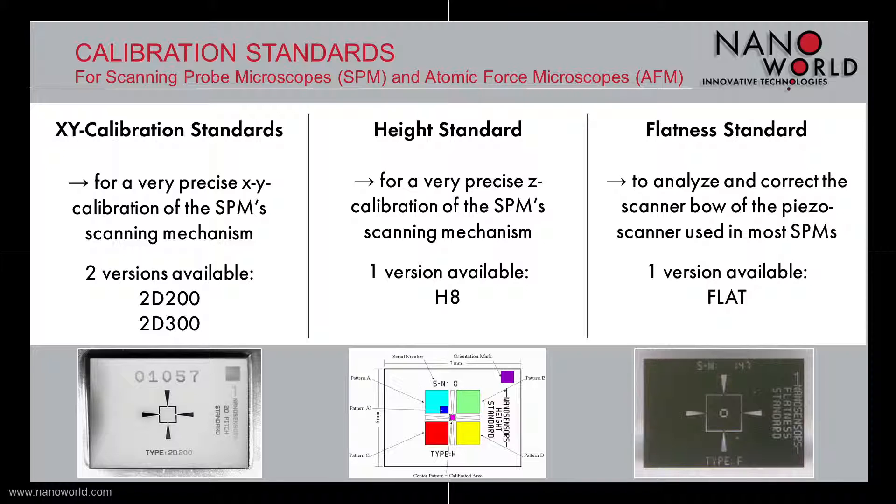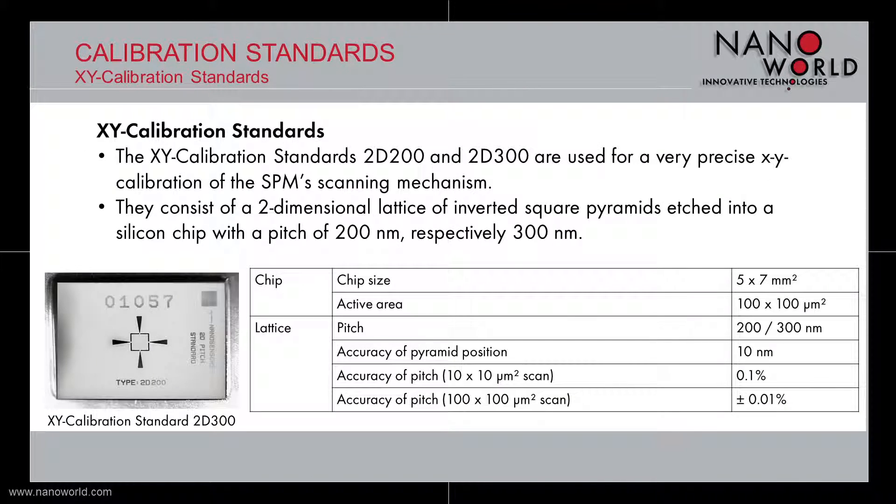The third category is intended to be used to analyze and correct the scanner bow of the piezo scanner used in most SPMs and AFMs. Let's start our description with the XY calibration standards.